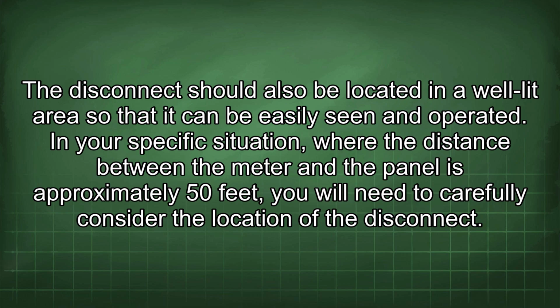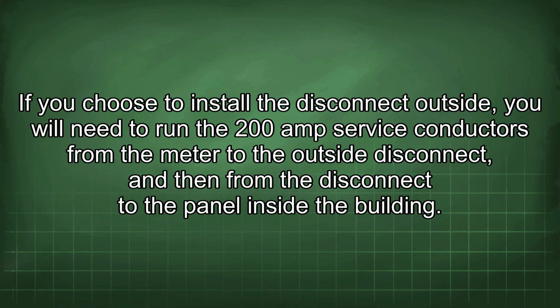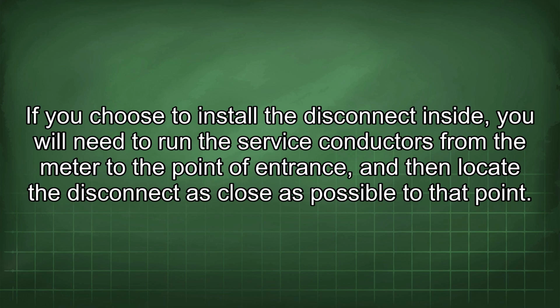In your specific situation, where the distance between the meter and the panel is approximately 50 feet, you will need to carefully consider the location of the disconnect. If you choose to install the disconnect outside, you will need to run the 200 amp service conductors from the meter to the outside disconnect and then from the disconnect to the panel inside the building. If you choose to install the disconnect inside, you will need to run the service conductors from the meter to the point of entrance and then locate the disconnect as close as possible to that point.